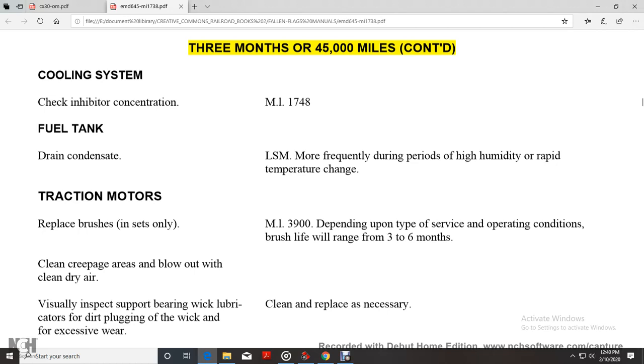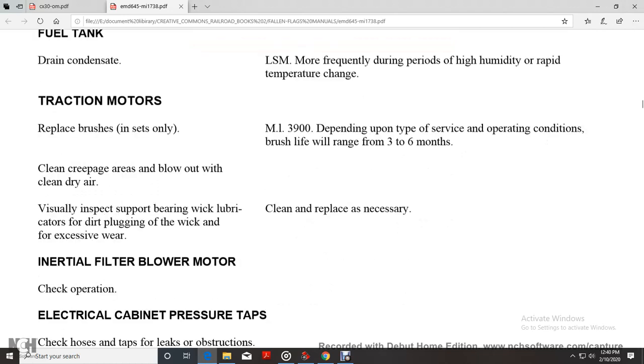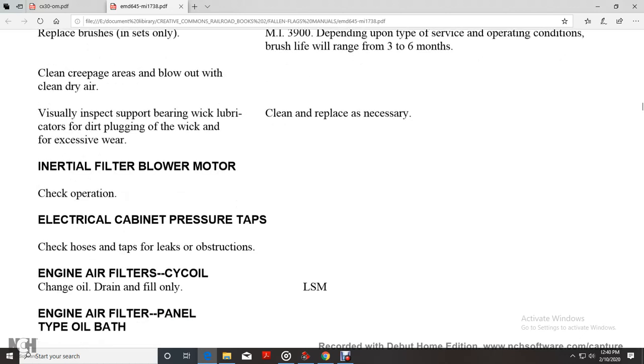Clean commutator and creepage areas; blow out with clean dry air. Visual inspection of support bearing wick lubricating: check the wick for dirt, plugging, or excessive wear. Check, clean and replace as necessary. Inertial filter blower motor: check for operation. Electrical cabinet pressure taps: check hoses and taps for leaks and obstructions.